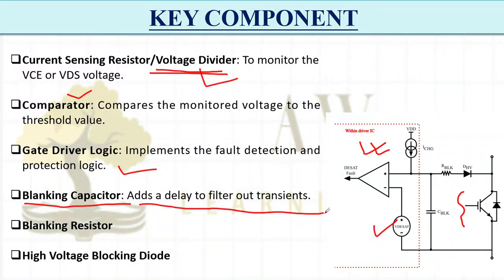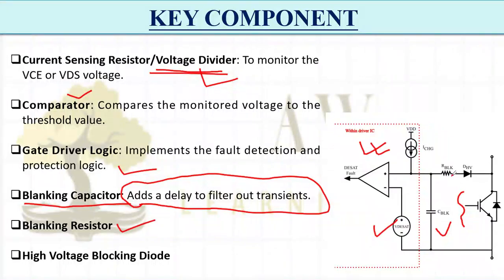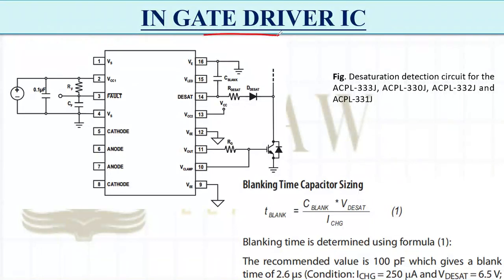An important component is the blanking capacitor, which adds a delay to filter out transients — this will be explained in detail shortly. There is also a blanking resistor and a high-voltage blocking diode. Now, looking at an example gate driver IC for IGBT protection, pin 14 provides inherent DESAT protection. You only need to add the blanking capacitor C_blk, R_dsat, and D_dsat externally to complete the circuit.